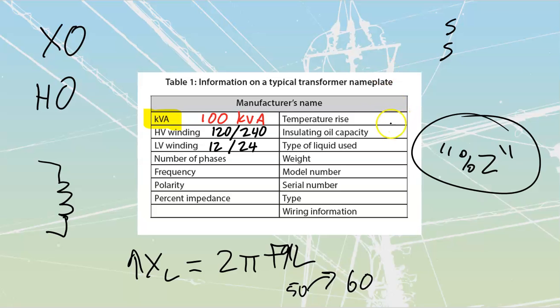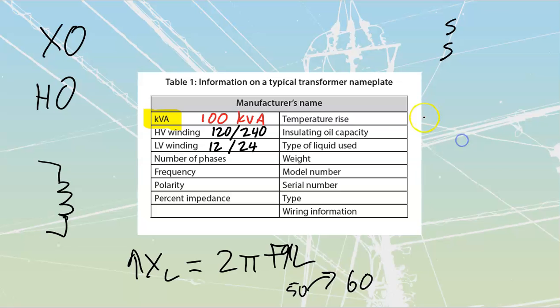Insulating oil capacity and type of liquid used. These are going to lead to a couple of factors. We've got environmental factors, the type of liquid, whether it's going to have PCBs, polychlorinated biphenyls inside of it, or whether it's going to have any other type of dangerous substances. We'll also want to know what the capacity is, because your transformer is going to be a pipe bomb. If you have got insulating oil, the reason we use oil is because oil is denser than air, right? If you pour a cup of oil out, it's not going to float up into the air, it's going to fall straight down, because it's denser than air, which means it's going to be more thermally conductive than air as well.